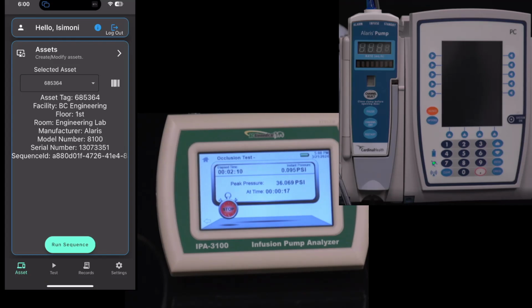The 3100 here, being a single channel, you can test a PCA pump, but you won't be able to count the number of boluses. You won't be able to get the bolus interval, things like that. A PCA pump will deliver, say, 5 milliliters at 10 or 20 milliliters per hour. We can measure that flow rate here, so you could test the flow rate and the volume dispensed of a PCA pump. But as far as doing bolus count and bolus interval, you would need the IPA 3400. That's a feature of that unit where it will provide measurements for every bolus that's delivered.